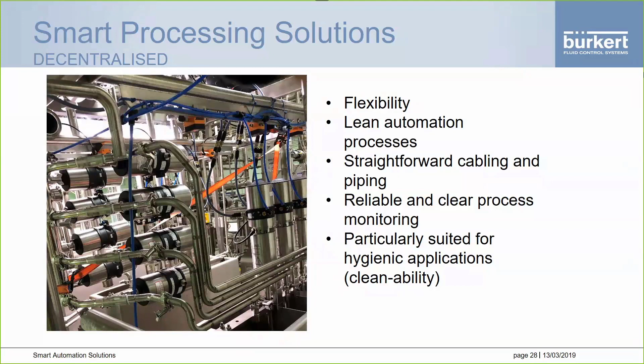When I talk about saving money, I'm talking about savings that can amount to literally tens of thousands of dollars, all depending on the size of the project. Taking this approach also means it's possible to eliminate all of the I/O cards at the PLC central level, and in doing so, many of the termination points and of course those costly junction boxes that are mounted in the field when using one of the more traditional approaches. With these new technologies available, it's even now possible to bring the diagnostics all the way down to the field level.